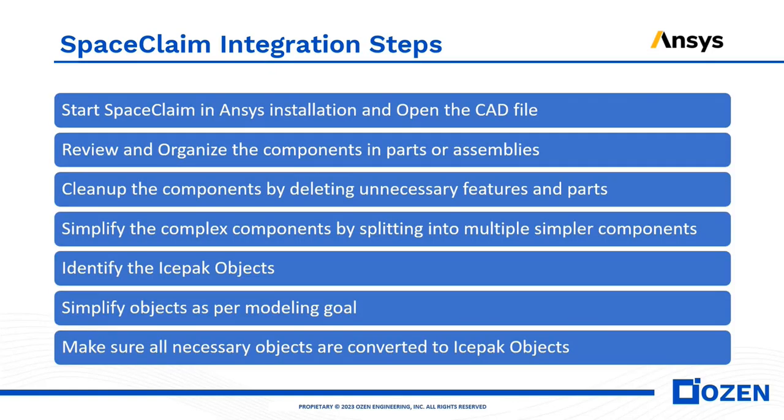Okay, so before going into the live demo, I will summarize some of the integration steps that we need to do. Remember, if you are going to clean the geometry using SpaceClaim, it should be the same version and release as the Icepak tool that you're using, right? Our recommendation is that you review and organize the components in parts or as assemblies, because these parts and assemblies will be brought into Icepak, so it will be easier for you to handle the model.